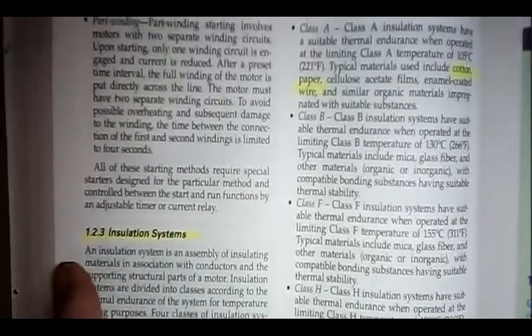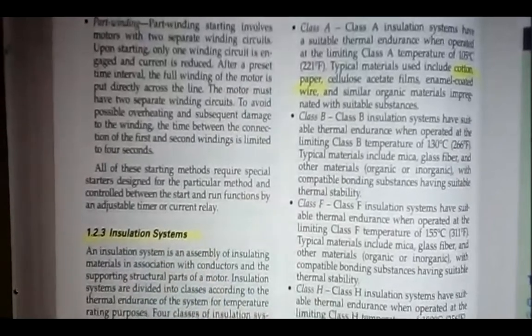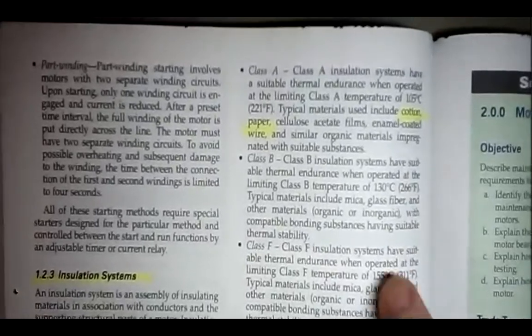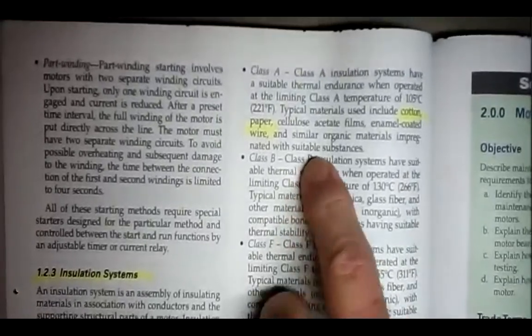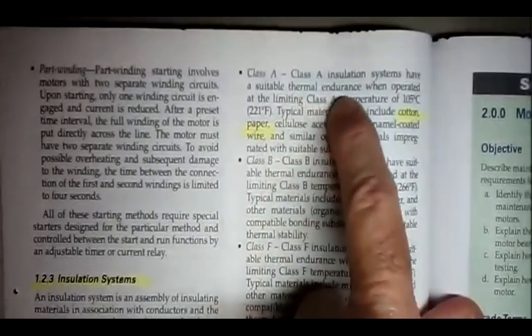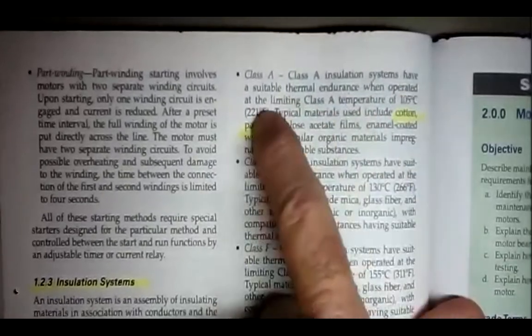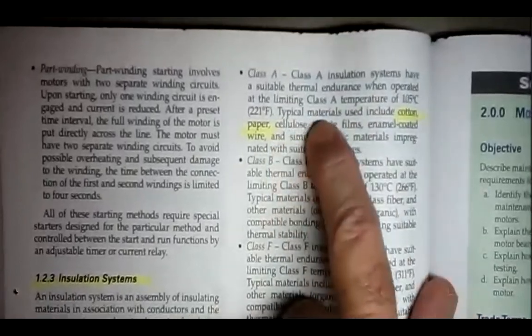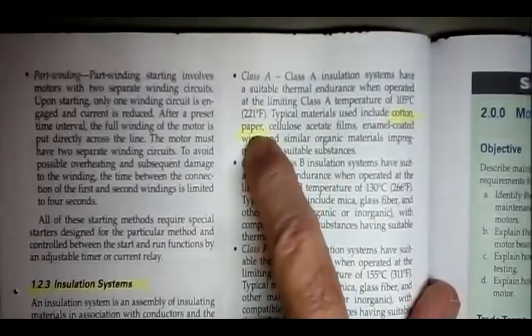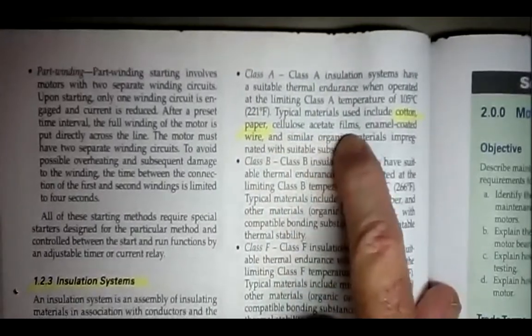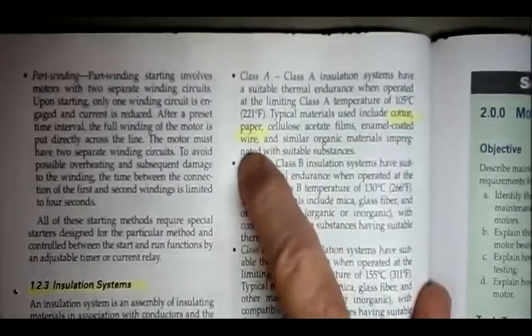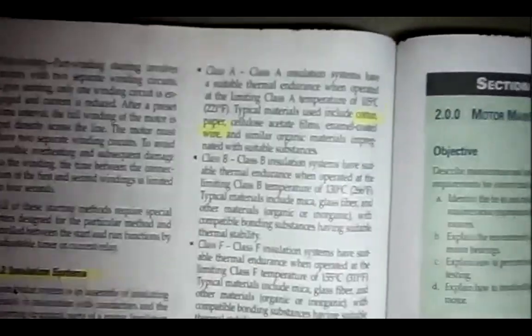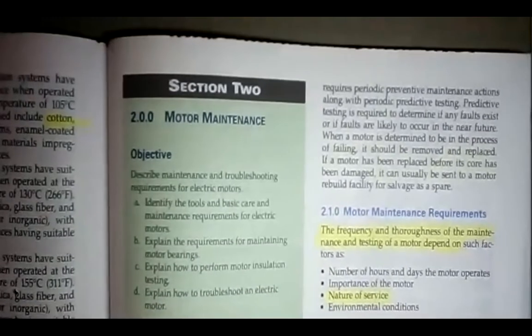Insulation systems, this is between the windings. The windings are varnished. It's a varnished wire. It's not a very thick insulation at all. Class A, class A insulation systems have a suitable thermal endurance when operated at a limiting class A temperature of 105 degrees Celsius. Typical materials used include cotton, paper, cellulose acetate films, enamel coating wire, coated wire. So those are the different types of insulation they use on a class A motor.